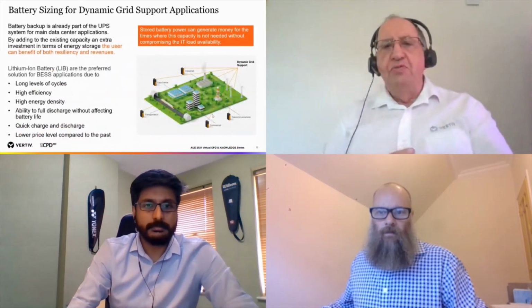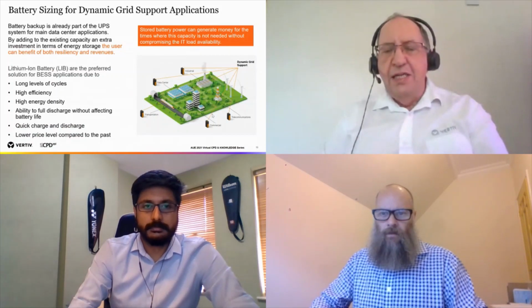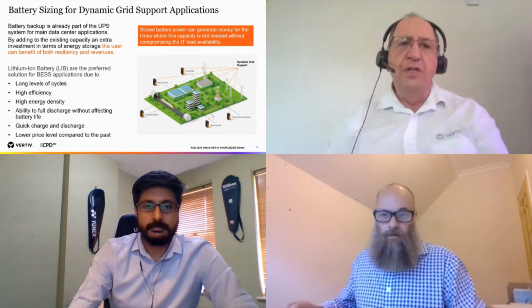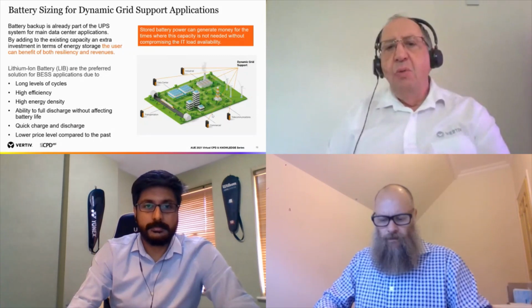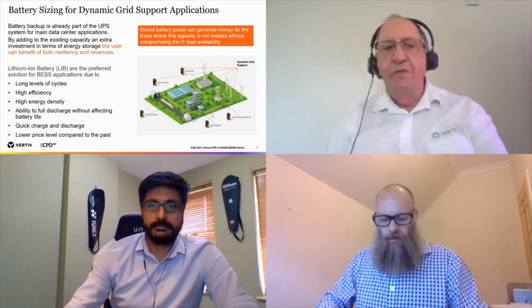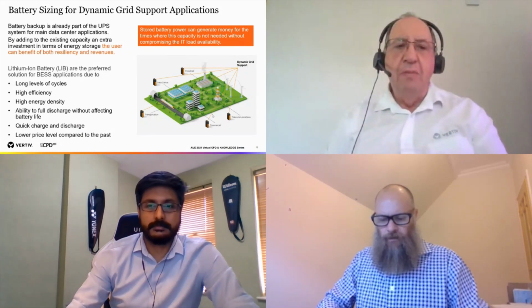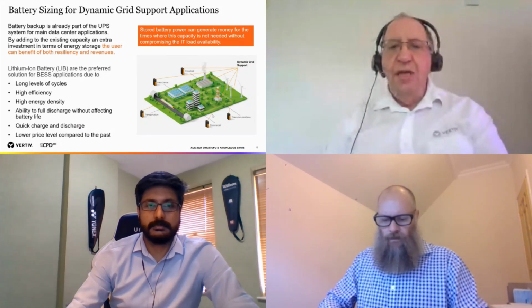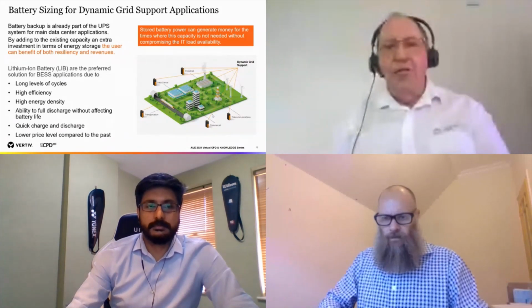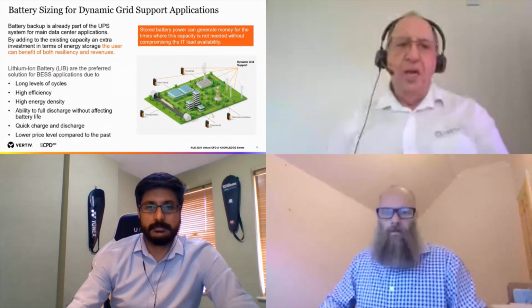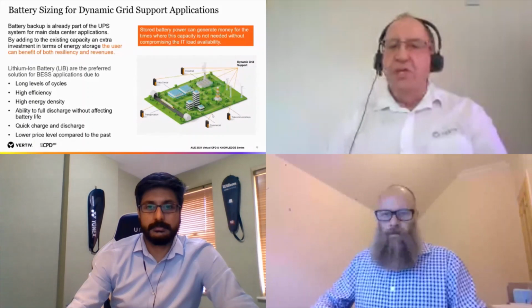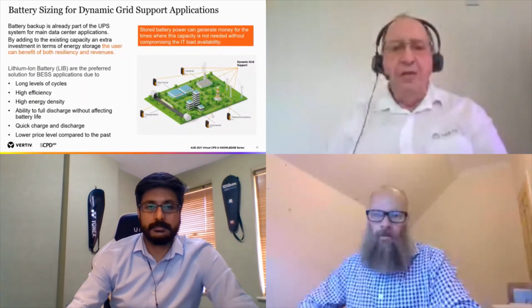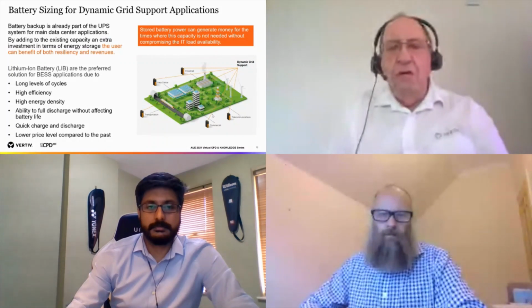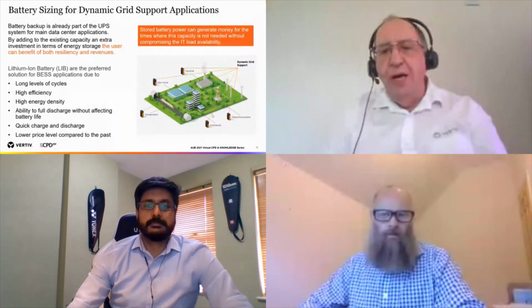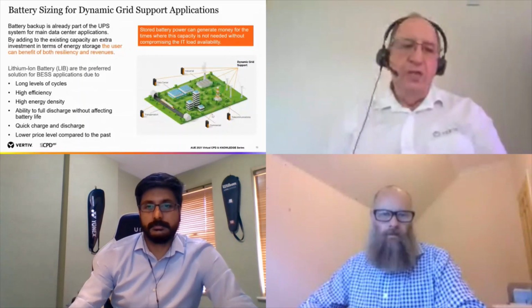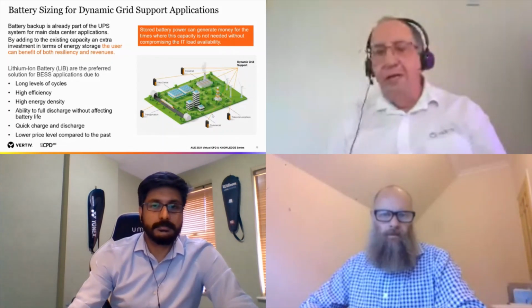The other thing that's going on is really a debate about how the grid is going to be formed as we go forward. And I'm aware that a number of universities have their own grid system within a campus. And we're talking to a couple of universities about that at this moment in time. But there are some considerations that you need to think about with regard to battery applications. And indeed, there are some storage applications that are coming online that could be of interest that don't involve batteries. We've got a couple of mechanical applications which are showing potential, let's put it that way, at this moment in time. So keeping Vertiv on its toes, we are available to advise on cycling and efficiencies and cost savings that could be made, etc., etc.